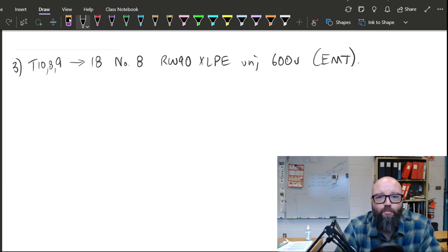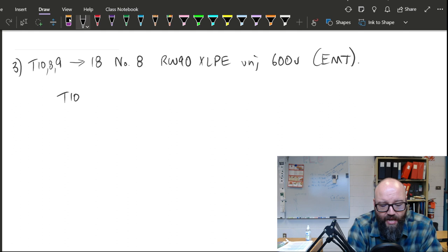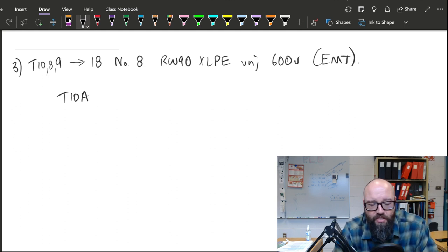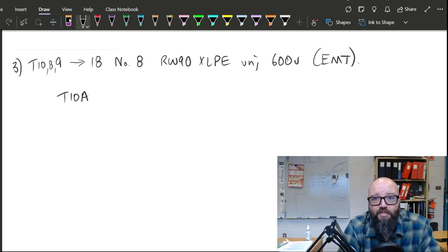So with this third method, we're going to keep the information the same, but we're simply going to use the Table 10A method, which is very similar to what we did with Table 6A. When we go to Table 10A, because we are dealing with stranded conductors here, as soon as I'm above a number 10, it's required that it's stranded. So Table 10A gives us the individual occupied area requirements of our single conductors, just like it did on Table 6A as well.